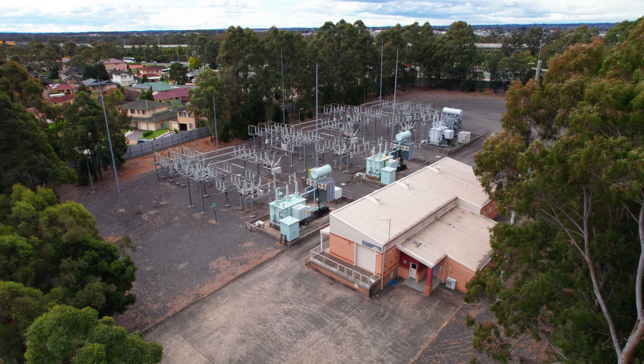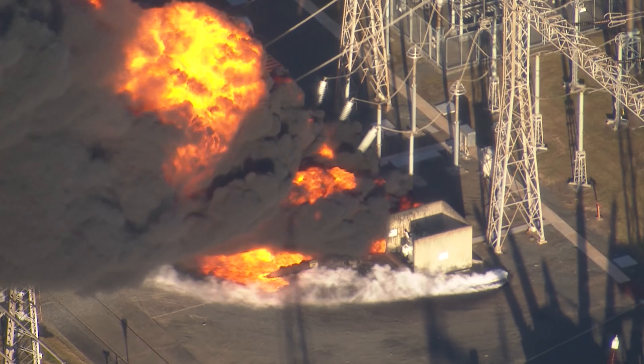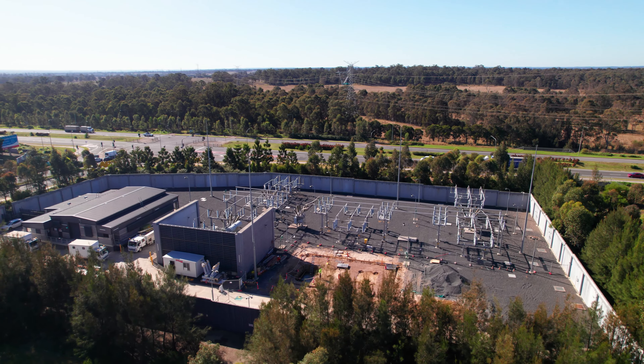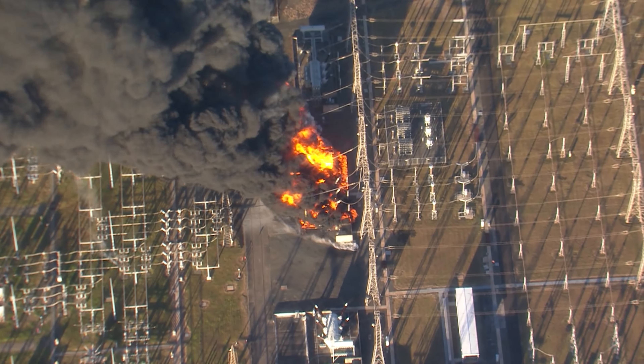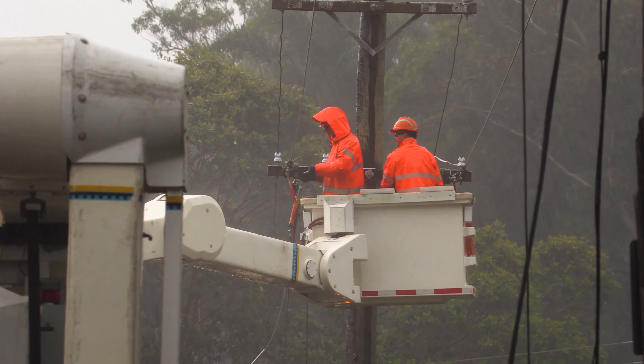It's also important to be aware of copper chrome arsenic poles, or CCA poles — these are identifiable by their green color. When damaged, CCA poles present a potential cancer risk, so they must be wrapped to allow for safe handling and personnel must wear the correct PPE for the task. Fire can also strike a substation. When this happens, there's a risk of toxic fumes being released from the burning of insulation, and equipment is often filled with oil. Never enter a substation without electrical distributor personnel present, as they know what additional risks are inside, including chemicals and other hazardous materials.